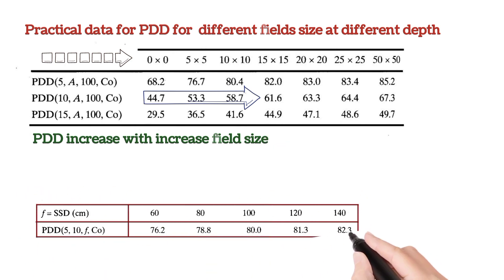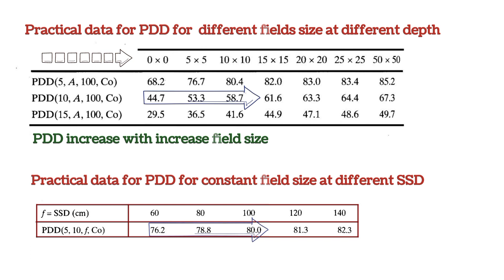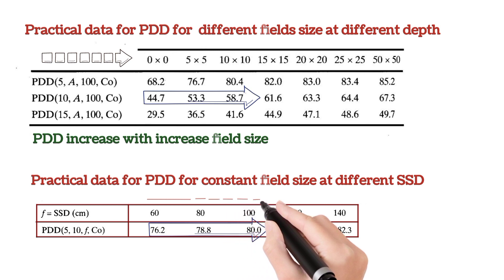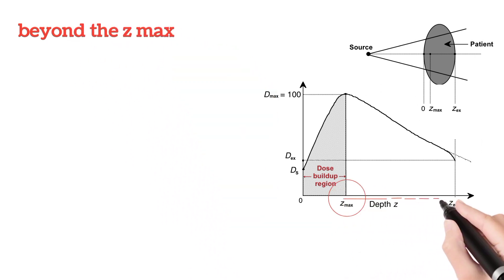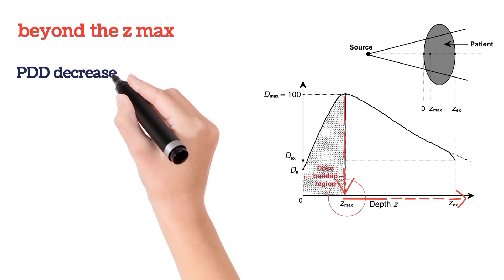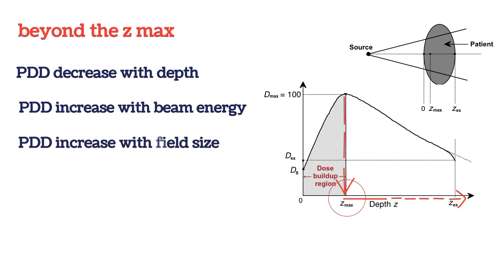This is the practical measured data for PDD for different SSD values. PDD is directly proportional to source-to-surface distance, meaning PDD value increases with increasing SSD. In summary: PDD decreases with depth beyond Z max; PDD increases with beam energy; PDD increases with field size; and PDD increases with SSD.